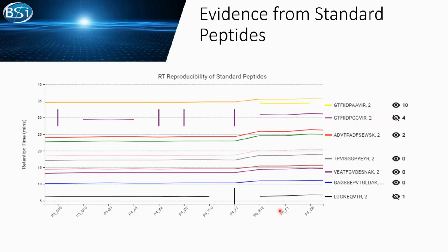Now we can say, okay, combining what we know from the previous slides, we can clearly say this problem is focused on the LC part. If I'm doing the experiment, I'd start checking if there is any leaking, any column pressure increasing, so I can identify my problem and solve that.